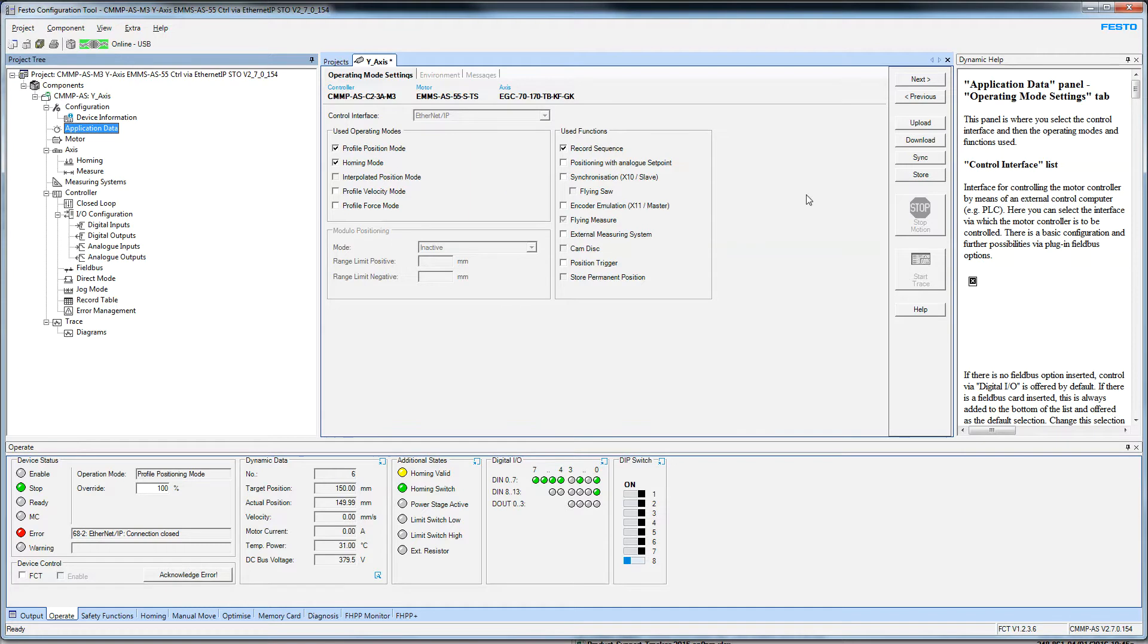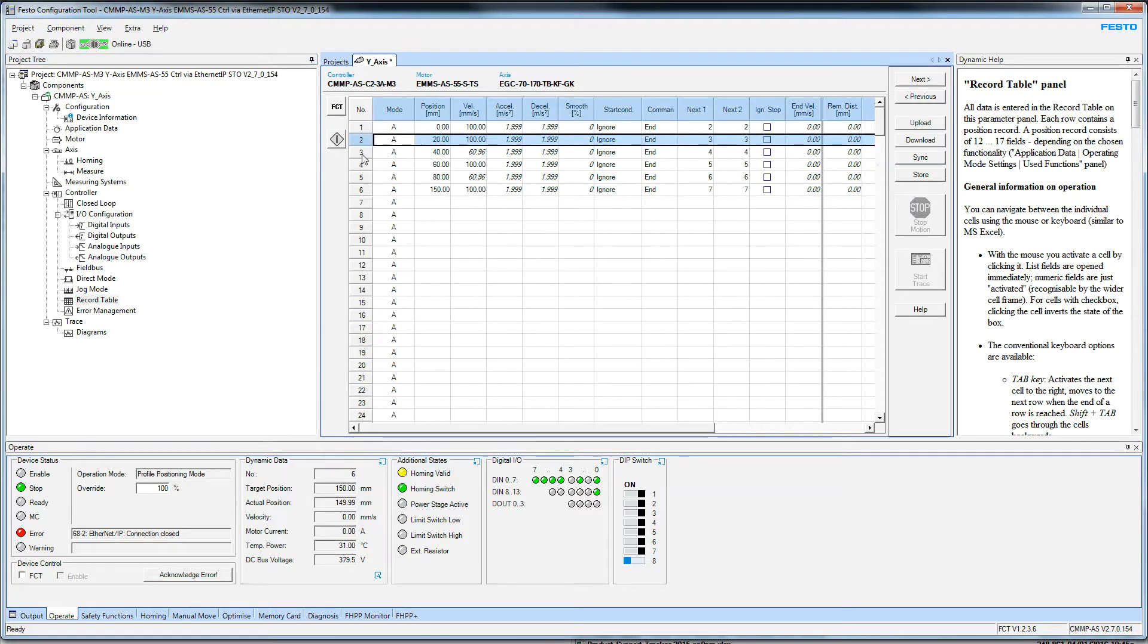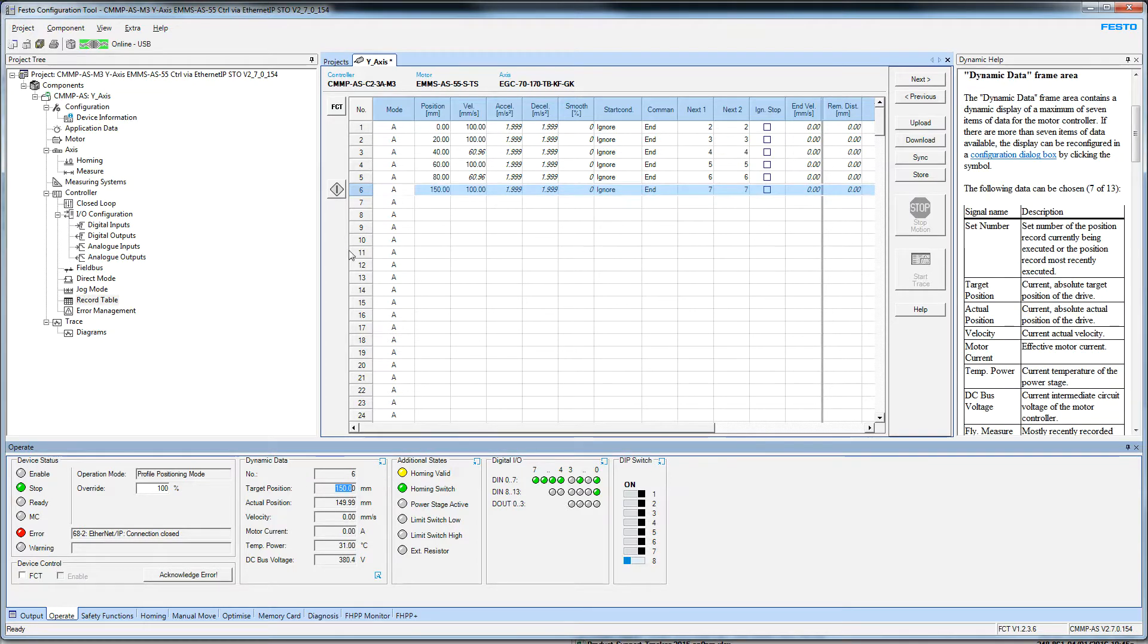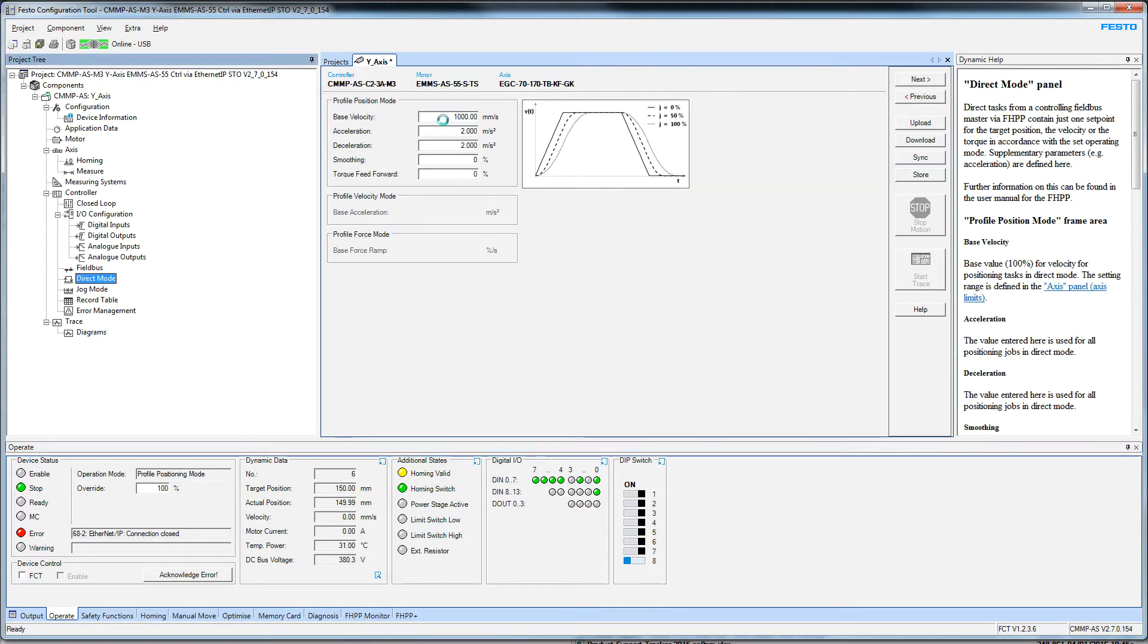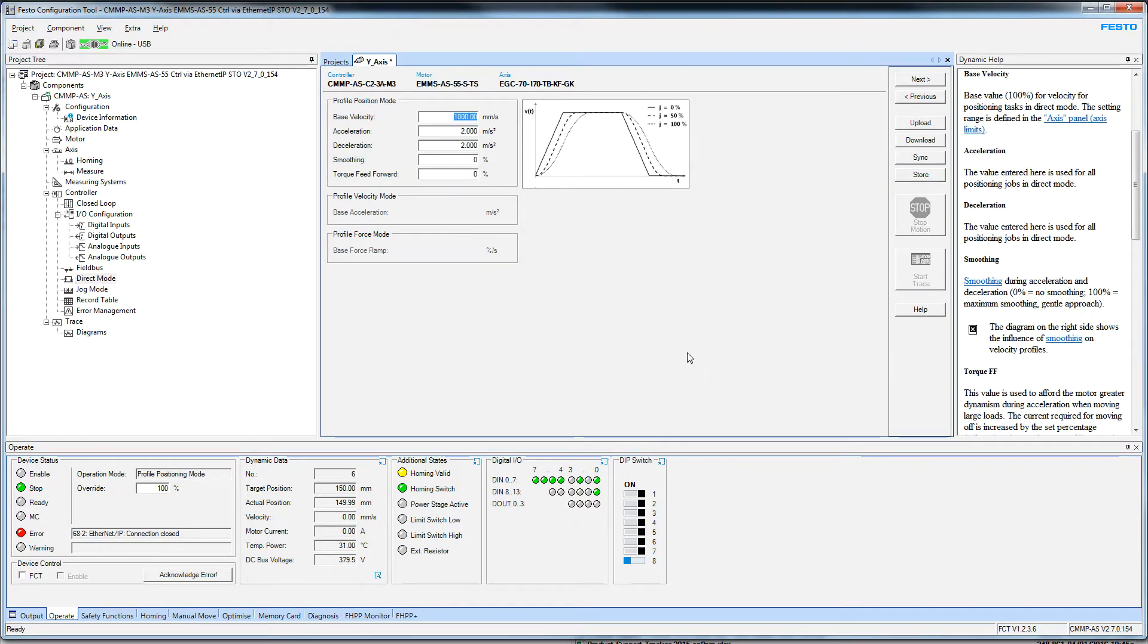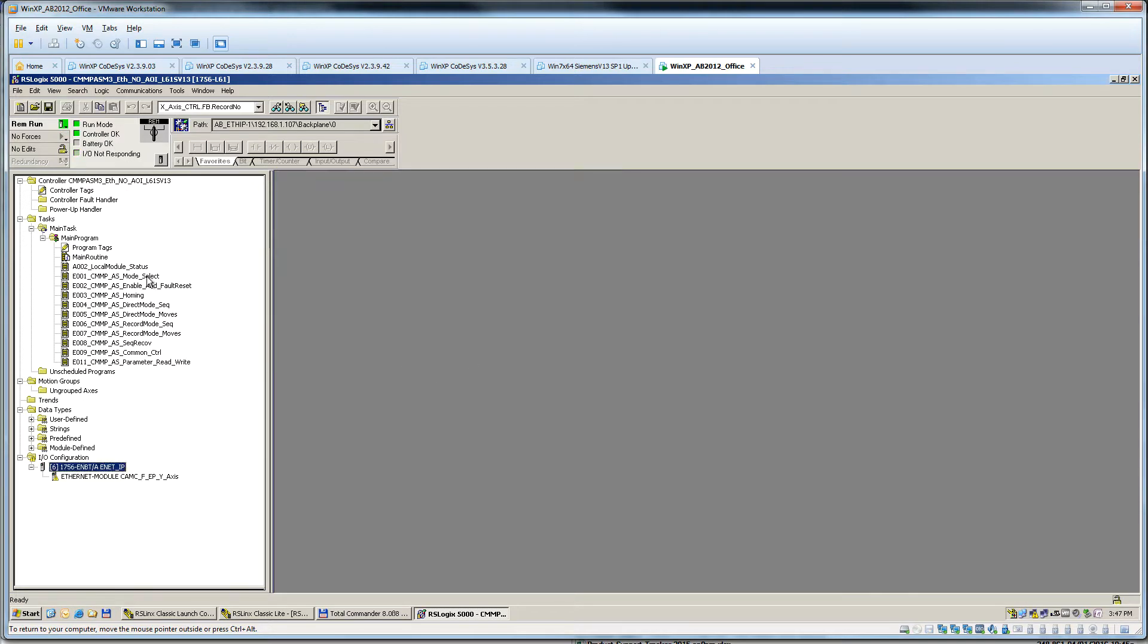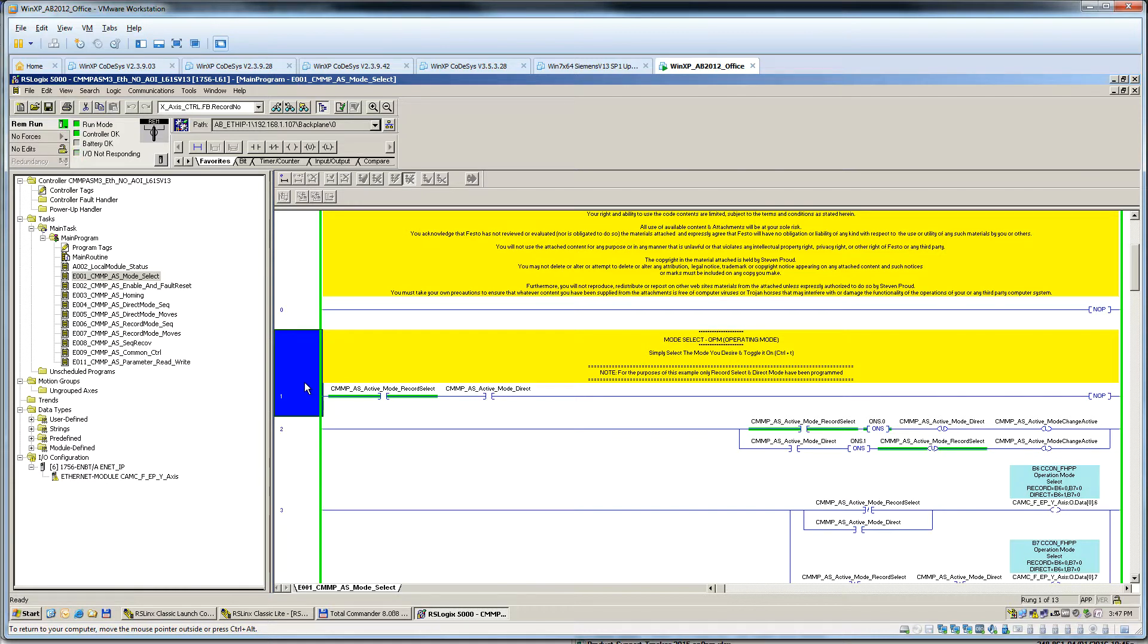The project itself has my code with six record mode moves. This is the record table where you set up some moves, then you call the record number, tell it to go, get a finish bit. Then there's direct mode where you specify an actual target position from the PLC and a velocity based upon this base velocity. You specify zero to 100%. This code is for debugging purposes. This is sample code. It's not meant to be used as a finished, complete product. You have to manipulate it for your application.